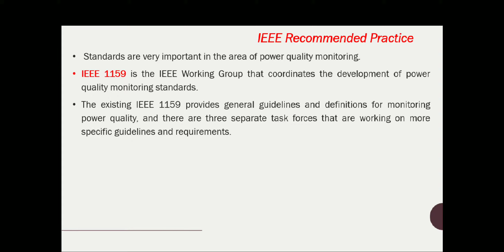I'll explain once again - IEEE 1159.1 is a working group developing guidelines for instrumentation requirements associated with different types of power quality phenomena. These requirements address issues like sampling rate requirement, synchronization, sampling accuracy, and number of cycles to sample, etc. IEEE 1159.2 is actually developing the characterization of different power quality phenomena.